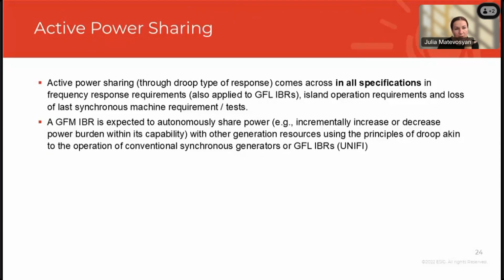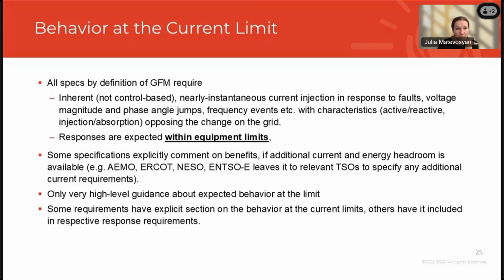Active power sharing: there is no specific requirement for active power sharing except in UNIFI, so other requirements don't call it out. But in all specifications, the frequency response requirement talks about droop type of response. And so in the frequency response requirements, in island operation requirements, and the loss of last synchronous machine requirement to test, this is where it's being looked at and droop type of response is expected.